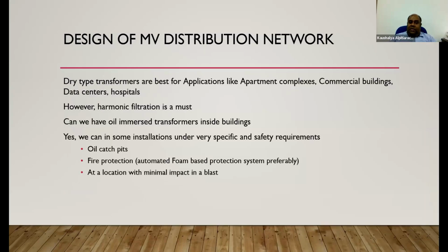Dry type transformers are the best for applications like apartment complexes, commercial buildings, data centers, hospitals, where you have very less or no capacitive switching or high inrushes. However, harmonic filtration is a must. Can we have oil immersed transformers inside buildings?